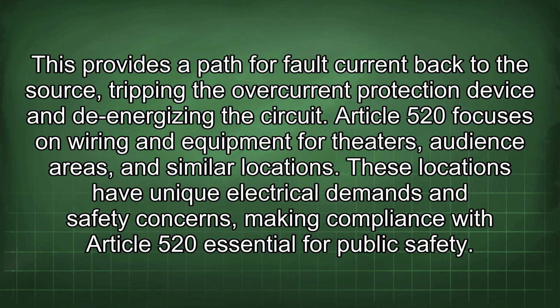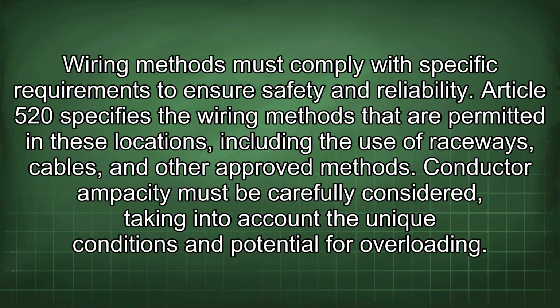Article 520 focuses on wiring and equipment for theaters, audience areas, and similar locations. These locations have unique electrical demands and safety concerns, making compliance with Article 520 essential for public safety. Wiring methods must comply with specific requirements to ensure safety and reliability. Article 520 specifies the wiring methods that are permitted in these locations, including the use of raceways, cables, and other approved methods. Conductor ampacity must be carefully considered, taking into account the unique conditions and potential for overloading.